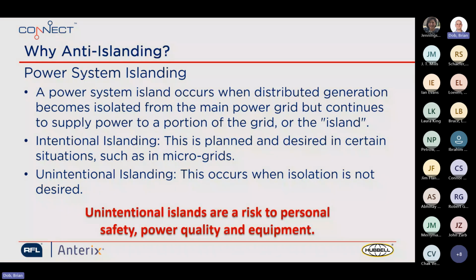So to start off, what is a power system island? Well, a power system island occurs when distributed generation, which is producing power and exporting that to the grid, becomes isolated from the utility substation and continues to supply power. This is referred to as a power system island.